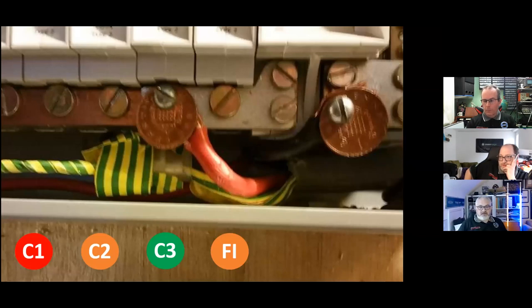You've got a CPC with a connector block. You've got an innovation of a one penny piece used to kind of act like a lug in some form to keep a stranded cable compressed against the bus bar so they could nick a supply from obviously a board that was full. So you're the inspector, you've gone in, you've checked your bonding, because any inspector doing an EICR should be checking the bonding first before doing anything else.